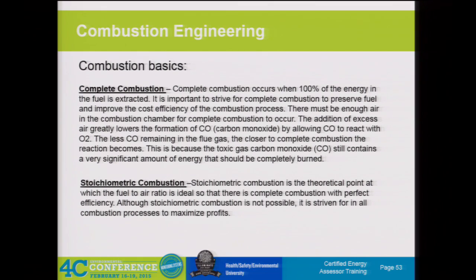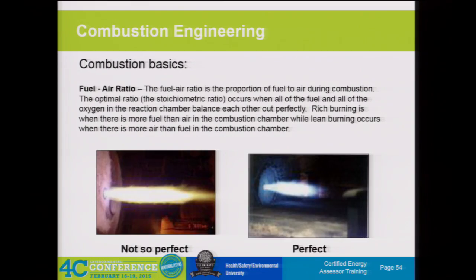So complete combustion—the stoichiometric combustion is that theoretical point for perfect efficiency. In our tuning and efficiencies, we're trying to get to that perfect level. And our biggest tool to do that is our air-to-fuel ratio. In most cases, the boiler temperature and turbulence—those design parameters—are fixed by the volume of the firebox, the arrangement of the burners, and where the combustion air is coming in and how that blends.